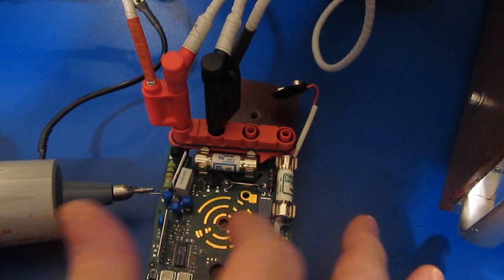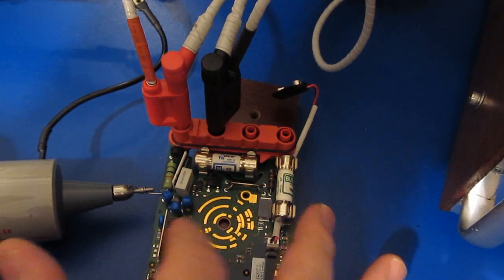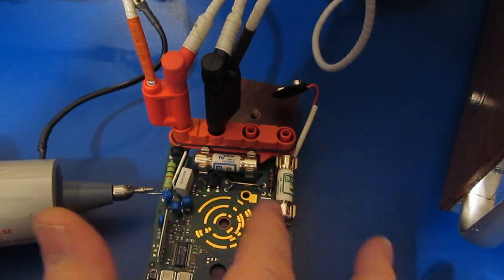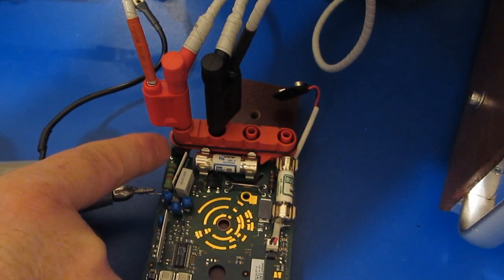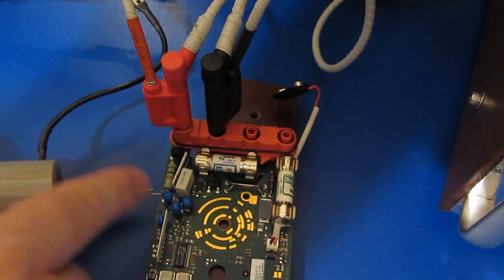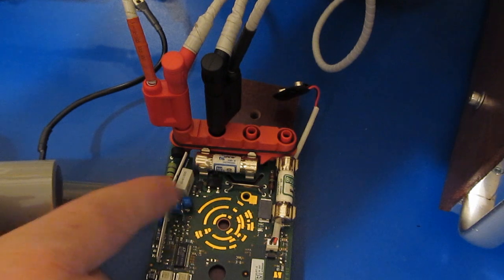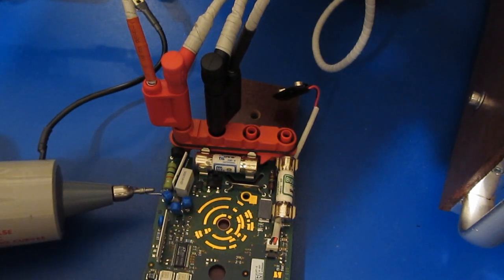So you notice I have the rotary switch removed, so our secondary clamp is not being activated right now. So currently what we have is the PTC in series with our surge rated resistor, in series with the MOVs, and that's what's going to make up our clamp.